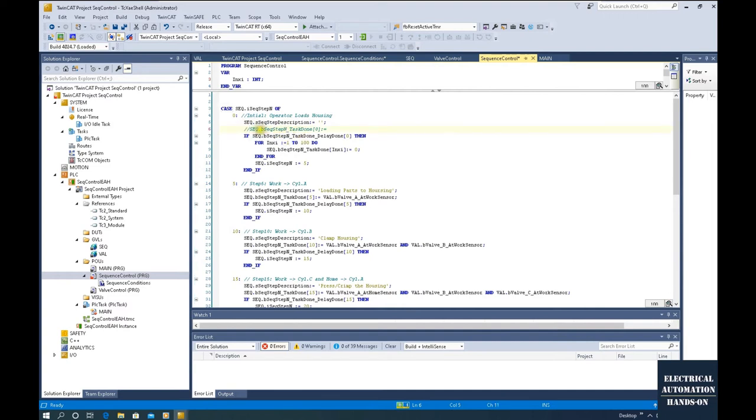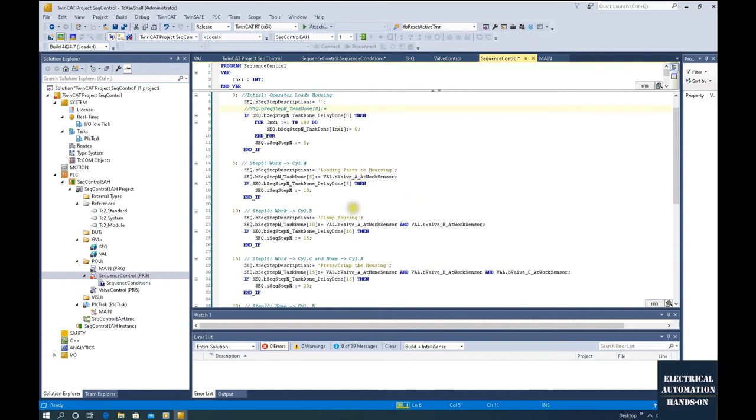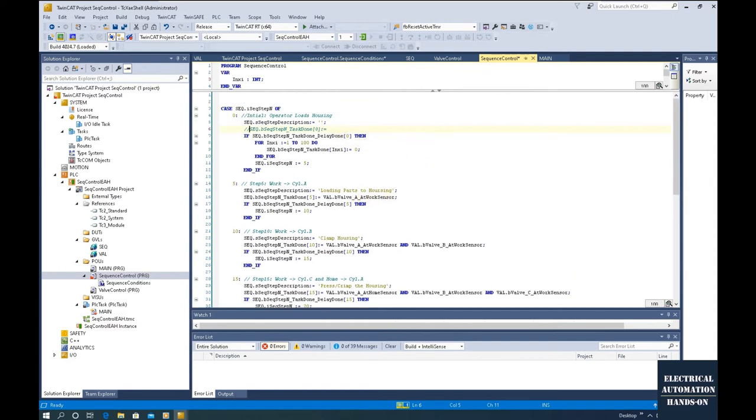So at zero, we can see what condition can control the step from 0 to 5. That is the initial condition. So basically for the machine at the beginning to control from 0 to the further step, we need to check out if all the tools are at home position to move forward. This home, you can define some tools, maybe the sensor turn on means at home, or sometimes the sensor turn off that at home. So in my case, all those valve A, B, C, D, those signals should add a home sensor. So firstly, I will define one tag that means the home.